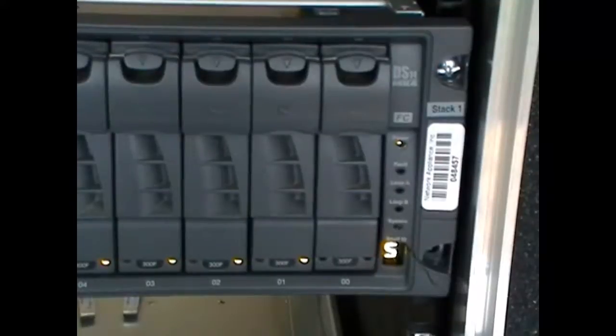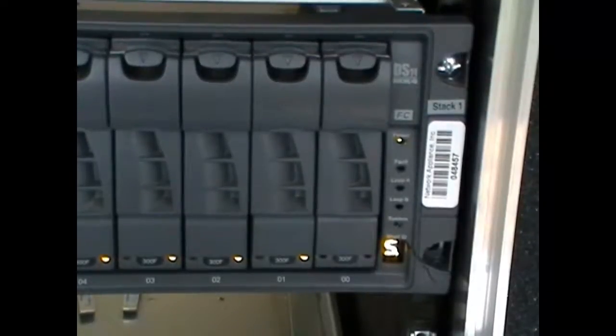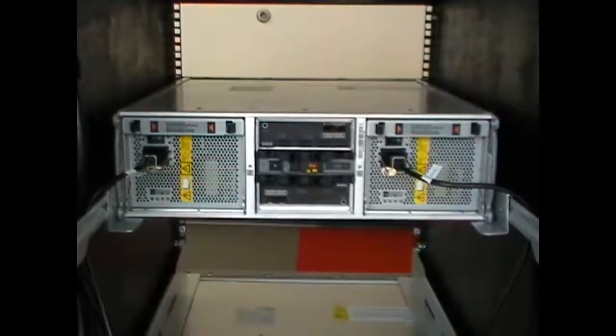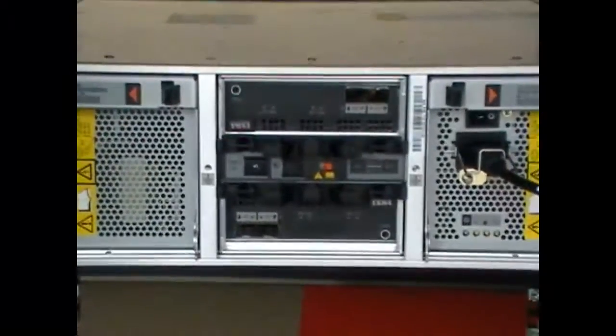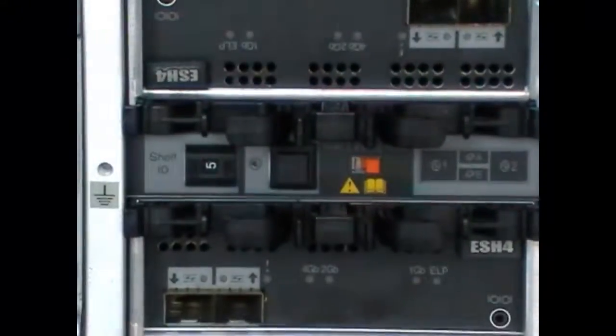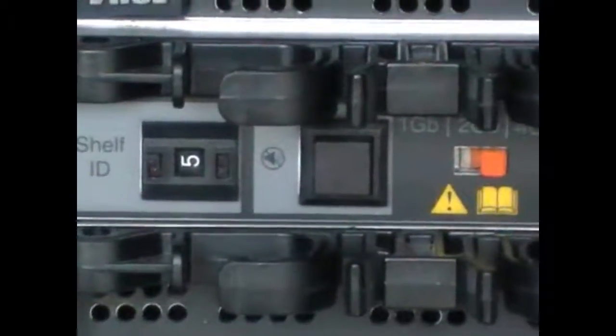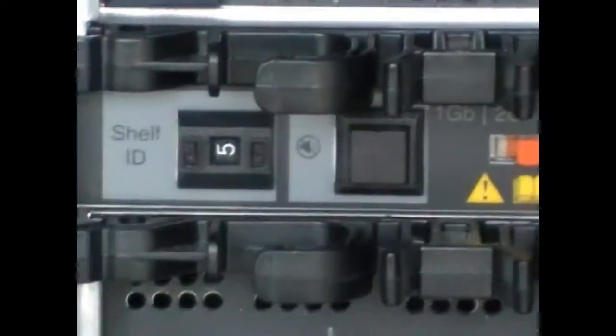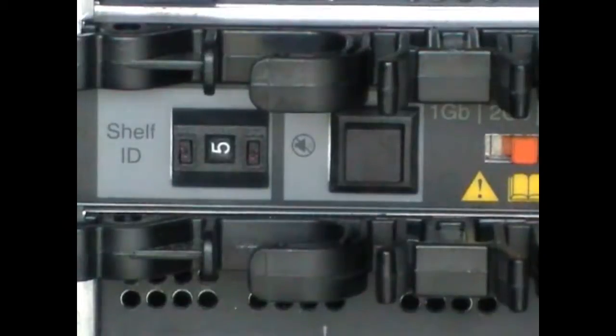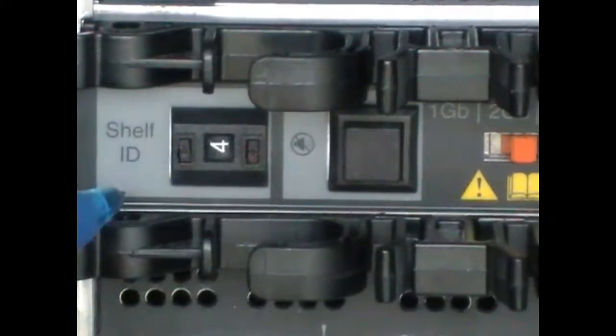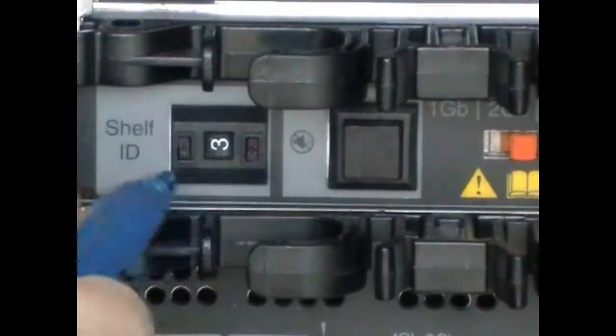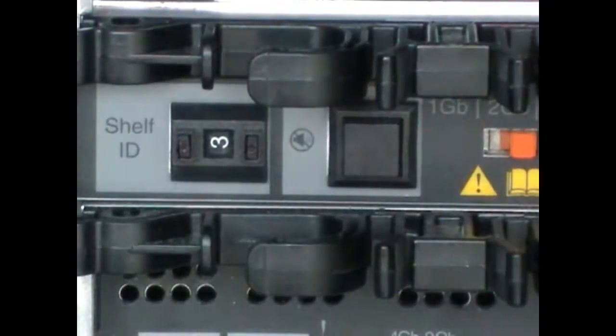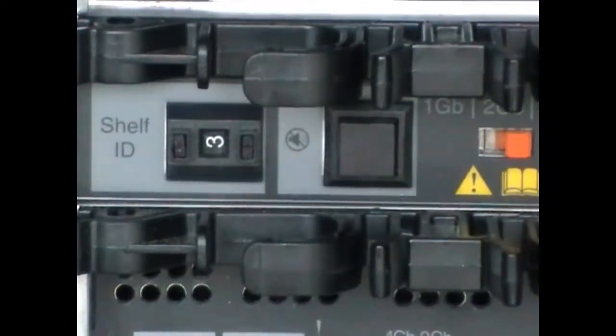This DS14 shelf has a shelf ID of 5, and we want to set it to 3. The first step is to turn the shelf off, which is why you need to set shelf IDs while the storage system is not running. The shelf ID is set using the switches in the back on the center plane of the chassis. Use a small object to press the buttons to move the ID forward or backward, and then power the shelf on.